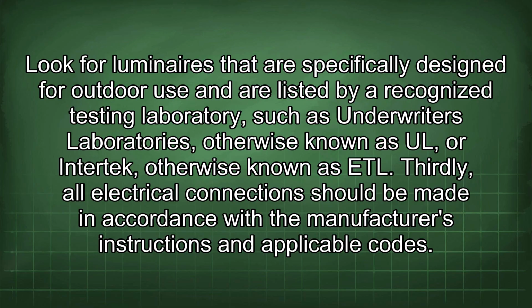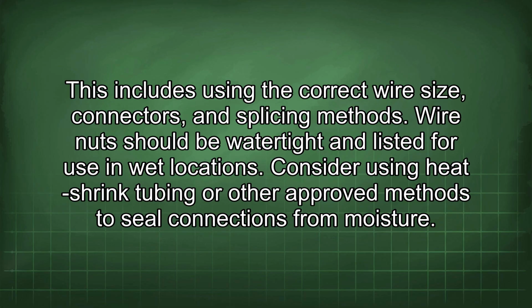Look for luminaires that are specifically designed for outdoor use and are listed by a recognized testing laboratory, such as Underwriters Laboratories, otherwise known as UL, or Intertek, otherwise known as ETL. Thirdly, all electrical connections should be made in accordance with the manufacturer's instructions and applicable codes. This includes using the correct wire size, connectors, and splicing methods. Wire nuts should be watertight and listed for use in wet locations. Consider using heat shrink tubing or other approved methods to seal connections from moisture.